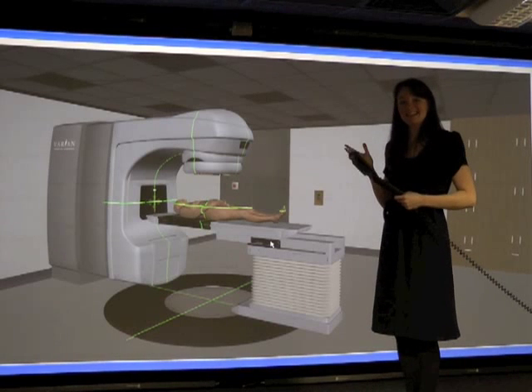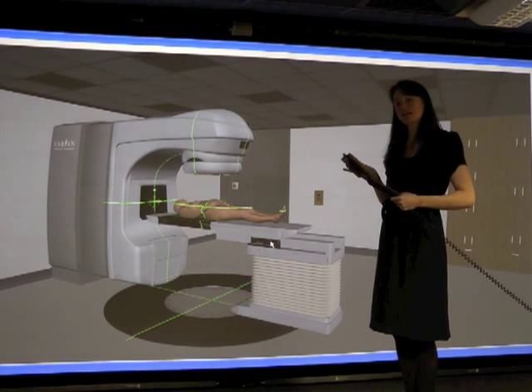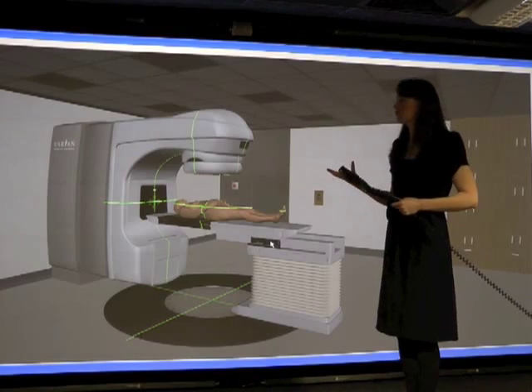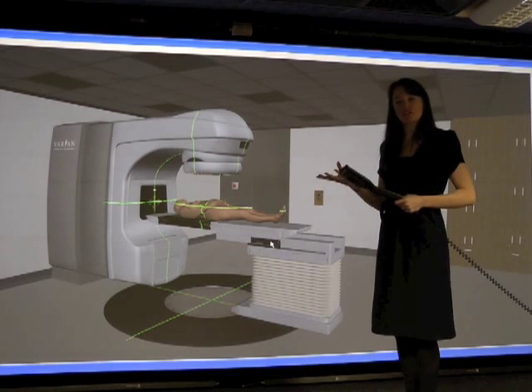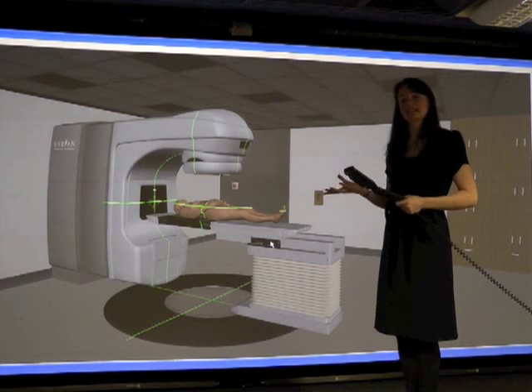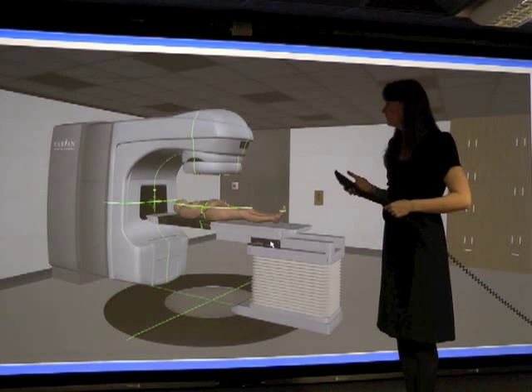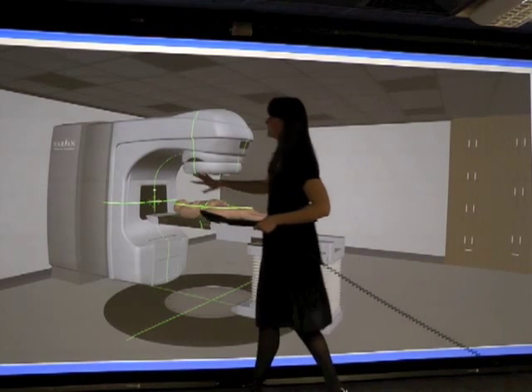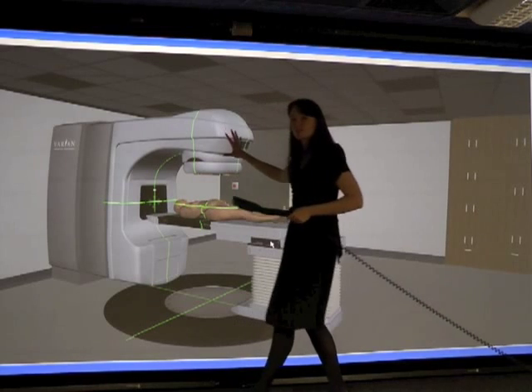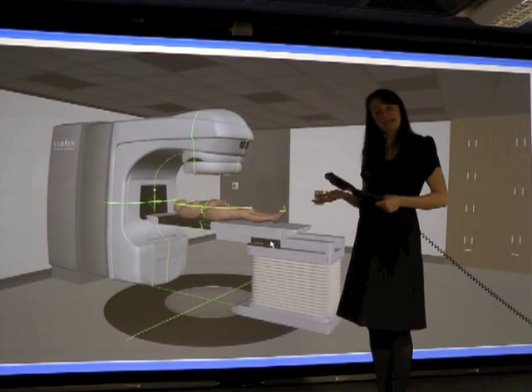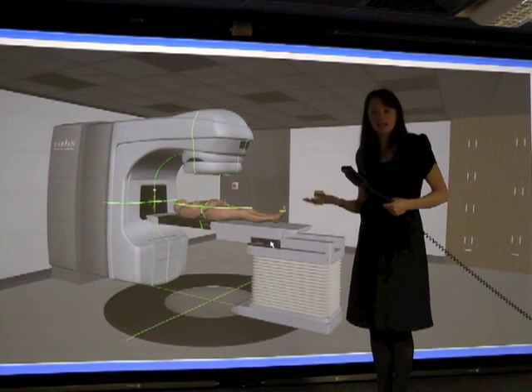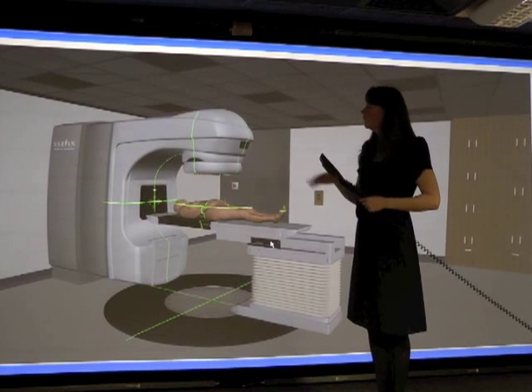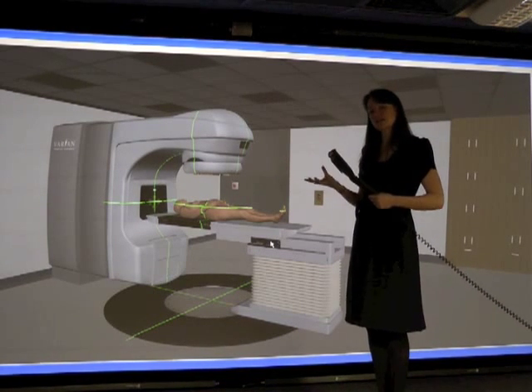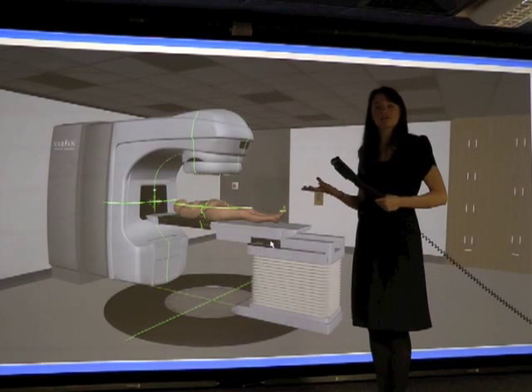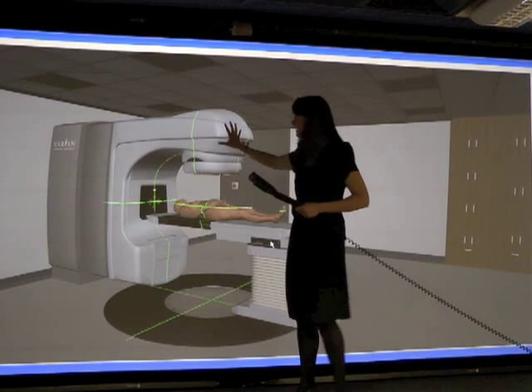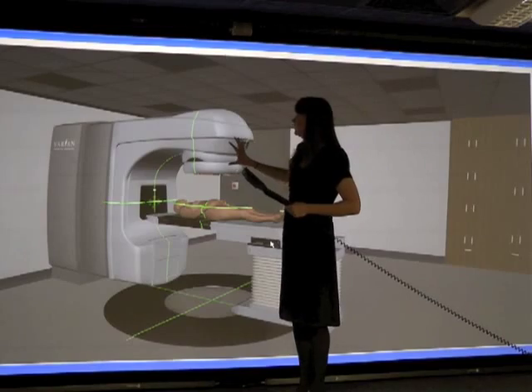We heat that filament using thermionic emission to generate electrons. Once those electrons are generated, they're accelerated, hence the name linear accelerator. Those electrons are accelerated through the waveguide and hit what we call a target, also made from tungsten, again with a very high atomic number. Once the electrons interact with the target, photons, or X-rays, are produced and then collimated, or configured.